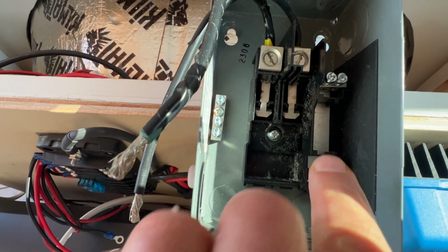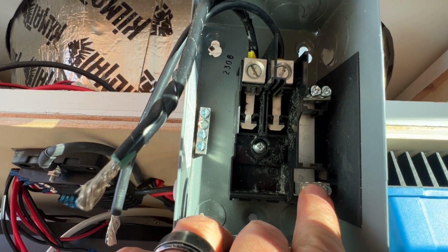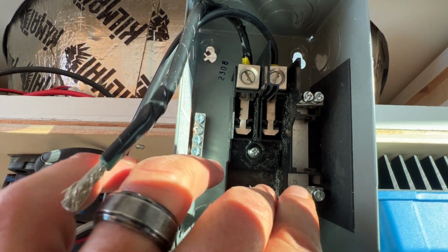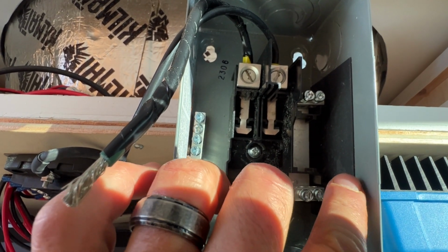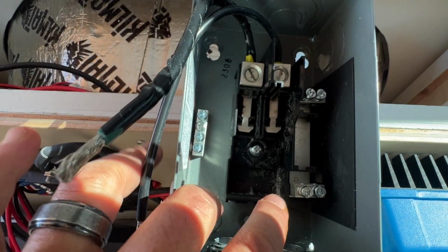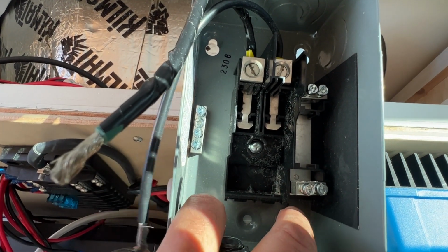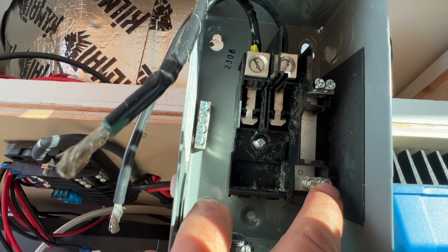Our negative, our neutral, is going to go right here to the neutral bus bar. Now this is not touching the circuit panel box, so this is what they call isolated. It sits up on this kind of plastic post, so only the white neutral wires will go here.